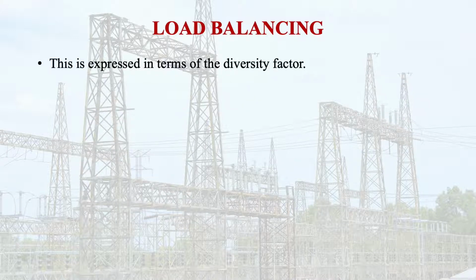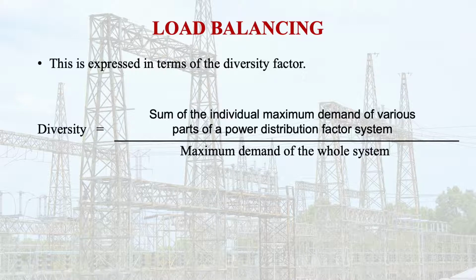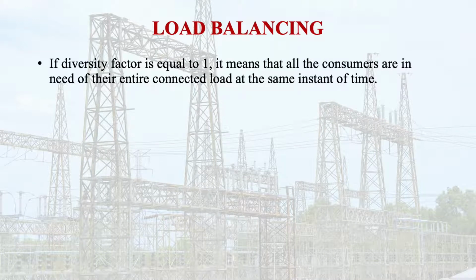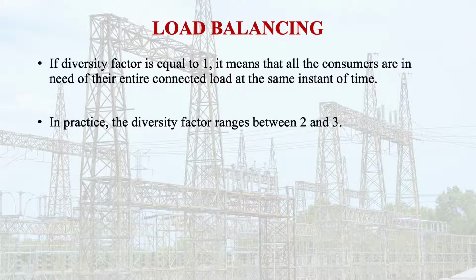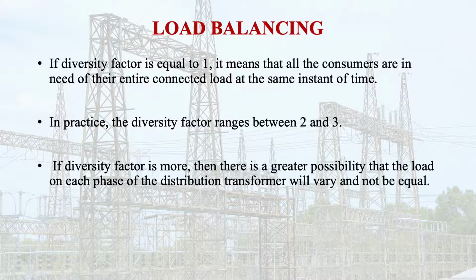So this is expressed in terms of the diversity factor, which is a very important term in the power system. If it is equal to 1, it means that all the consumers are in need of their entire connected load at the same instant of time. So this is the diversity factor. In practice, the diversity factor ranges between 2 and 3. If the diversity factor is more, then there is a greater possibility that the load on each phase of the distribution transformer will vary and not be equal.